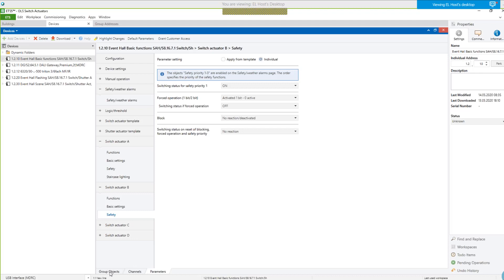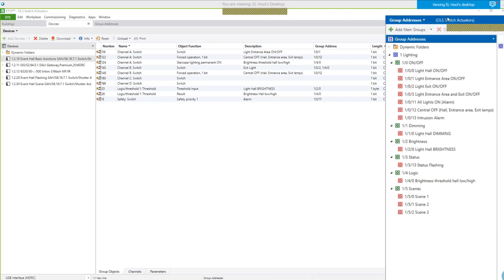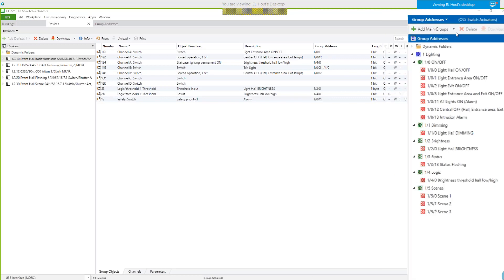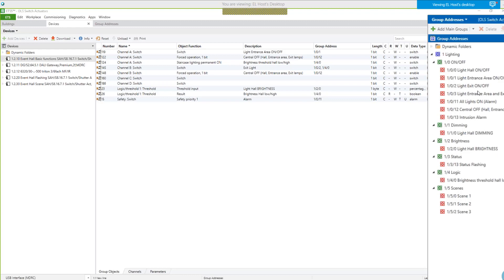Let's have a look at the group objects and the group addresses I have created. Starting with channel A, I can operate it locally. Here is the first operation — central off is group address 1/0/12. It belongs not only to channel A but also to channel B, and it comes from anywhere to switch off all lights with higher priority than local switching. Then let me come to the threshold functions and show this in the parameters.